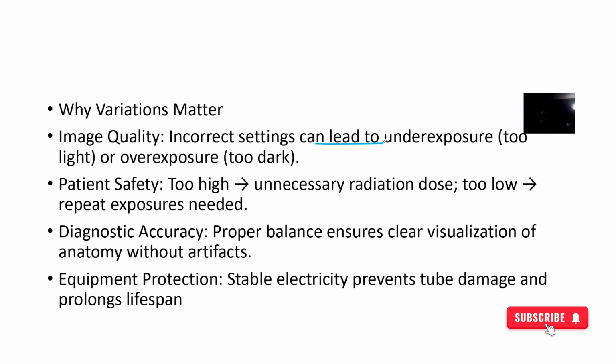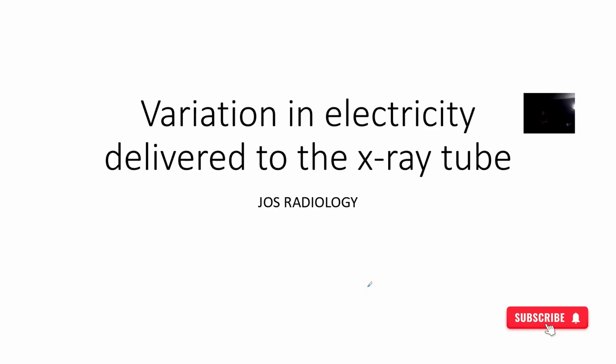Patient safety could be too high, leading to unnecessary radiation dose, or too little, where you now have images that are not clear and you have to now still bring the patient and expose them to the same process again. So diagnostic accuracy, proper balance ensures that you have a very clear image which you can work with. Equipment protection. So stable electricity prevents tube damage and also prolongs the lifespan.